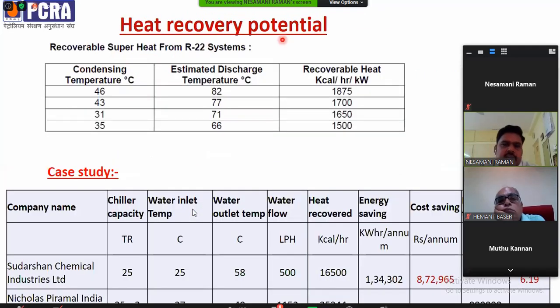This is a heat recovery potential. For ammonia and R410, for all refrigerants, we have a potential. For the sake of explaining, I have taken only one sample, R22 systems. For every condensing temperature and discharge temperature of the compressor, it is almost 1875 kilocalories per hour per kilowatt. So kilowatt means capacity; we need to multiply the capacity with the actual kilowatt. This much heat they could recover.